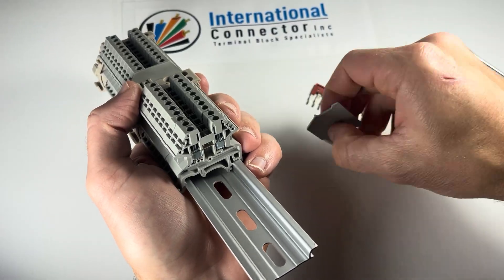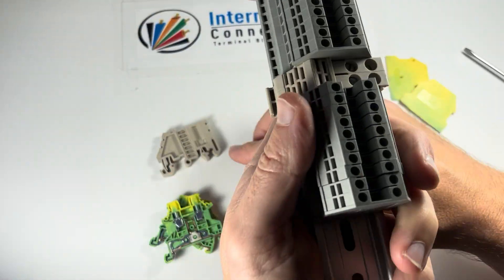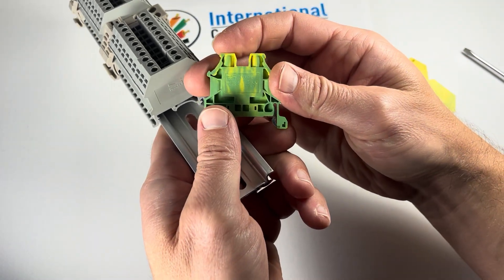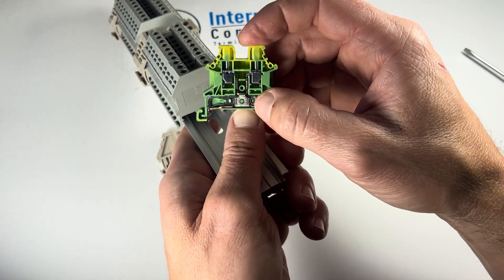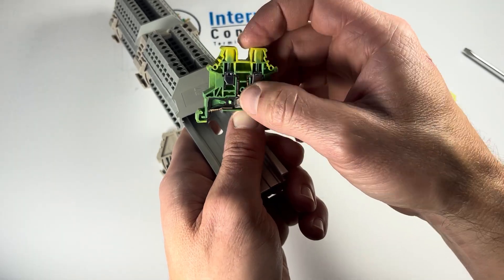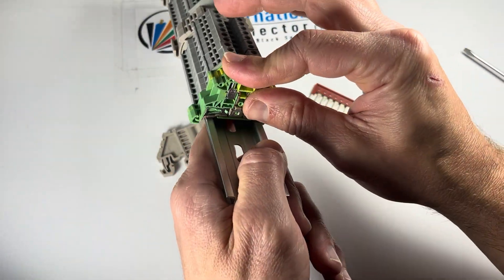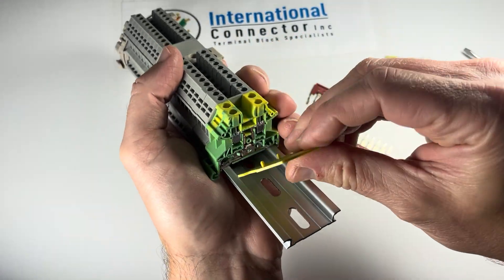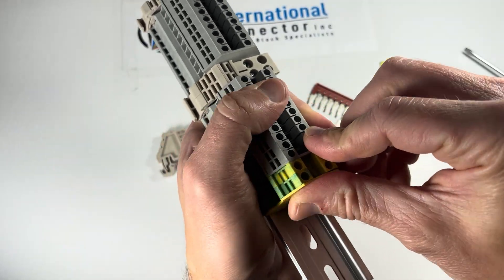So I did 10 and 10. Now, depending on where you'd want a ground block — you see the ground block here. This is a DK 4NPE, so that handles up to 10 gauge. This one's got metal all the way to the bottom into the foot, so it's a lot more substantial of a block. Now that's connected to the rail — it's an earth ground block. So now everything gets grounded to this rail and you can ground it to the box. If you want to do them separately, we've got two end covers — it's a DK 2.5NC-PE, and that covers it up nicely.